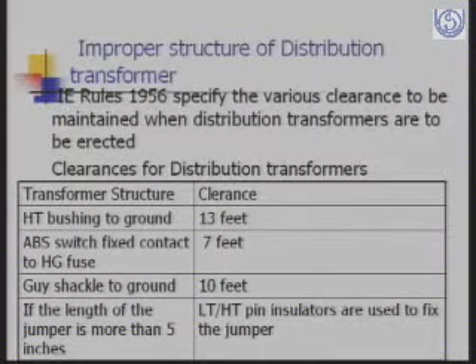So the clearances for distribution transformers are: the transformer structure, HT bushing to ground should be 13 feet. The ABS switch, fixed contact to HG fuse should be 7 feet. The guy shackle to ground should be 10 feet. And if the length of the jumper is more than 5 inches, then LT-HT pin insulators are to be used to fix the jumper.